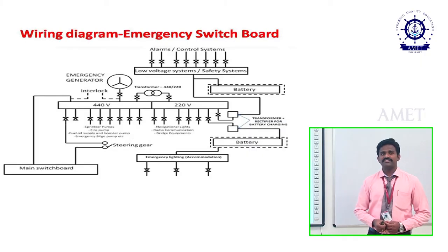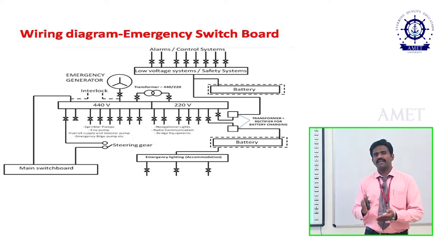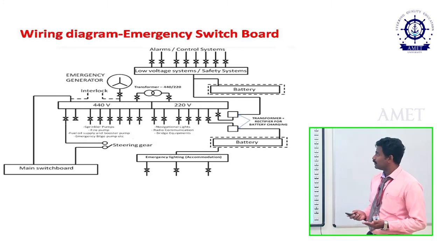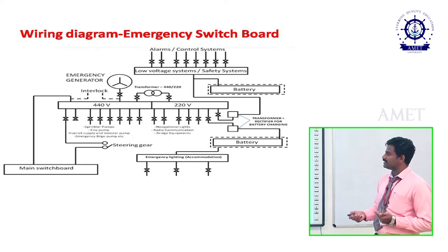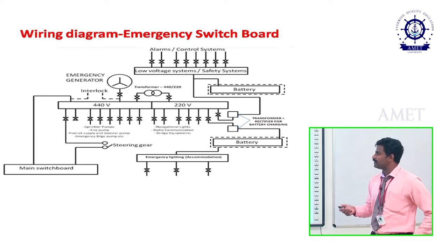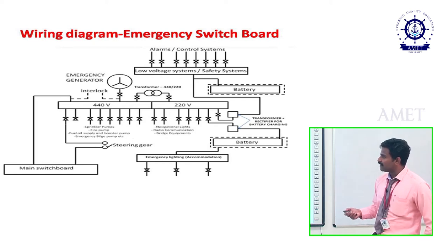This is the wiring diagram of the emergency switchboard. The emergency switchboard is split into two voltage sections: 440V and 220V. The main switchboard supply is connected to the 440V section. There is a switch connected between the main switchboard and the emergency switchboard, and the emergency generator connects to the emergency switchboard.